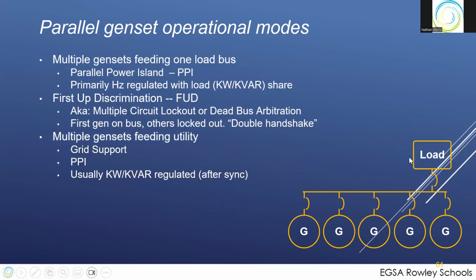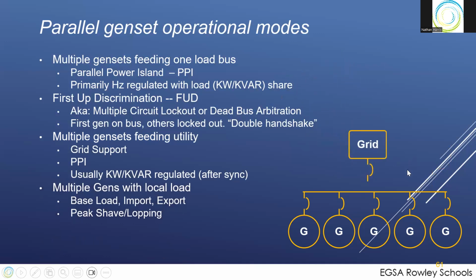These multiple gens then feed a utility, and there's the grid. And in this case, we should have a local load breaker here too. Sorry, I had a mistake on my animation. There's a load that should be here. The last example is multiple gens with the load and the grid. In this case, you get your export, import, peak shave, things like that with the grid, and your local load should be here. I have an animation error here. So multiple gens feeding a load, multiple gens feeding the grid, multiple gens feeding both a load and a grid. All these require increasingly complex control systems.